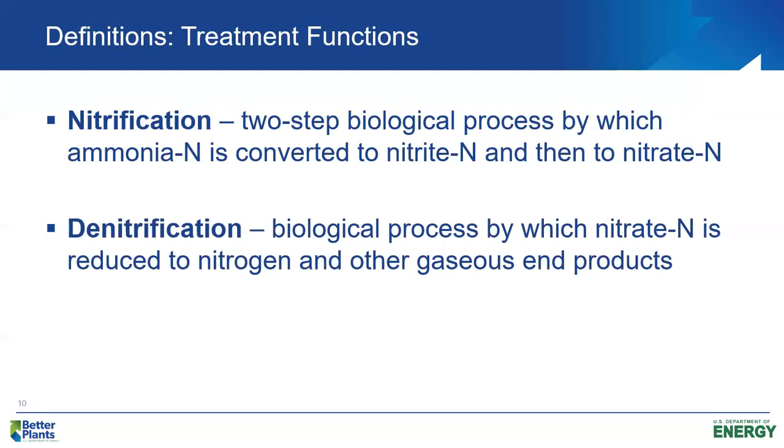Nitrification simply is nitrogen conversion. We're converting ammonia nitrogen to nitrate nitrogen. And obviously, we'd much rather discharge nitrate nitrogen to a stream than ammonia nitrogen, because I always say ammonia nitrogen has three strikes against it. Ammonia nitrogen is toxic to fish. Ammonia nitrogen exerts a high oxygen demand, and it can also promote eutrophication or excessive aquatic plant growth in the receiving stream. Nitrate nitrogen is not toxic.